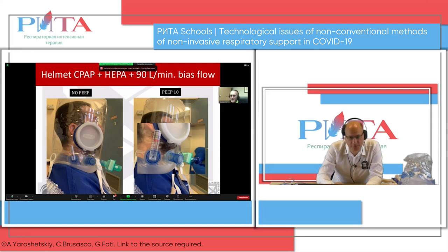Very interesting information. You put 10 instead of 15 because the flow is high. You have the HEPA filter, and the HEPA filter provides additional resistance. I see, and then the PEEP goes up.